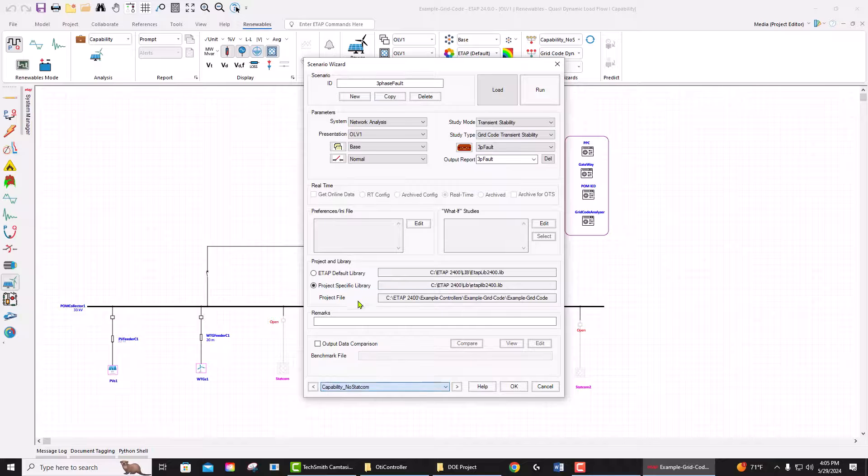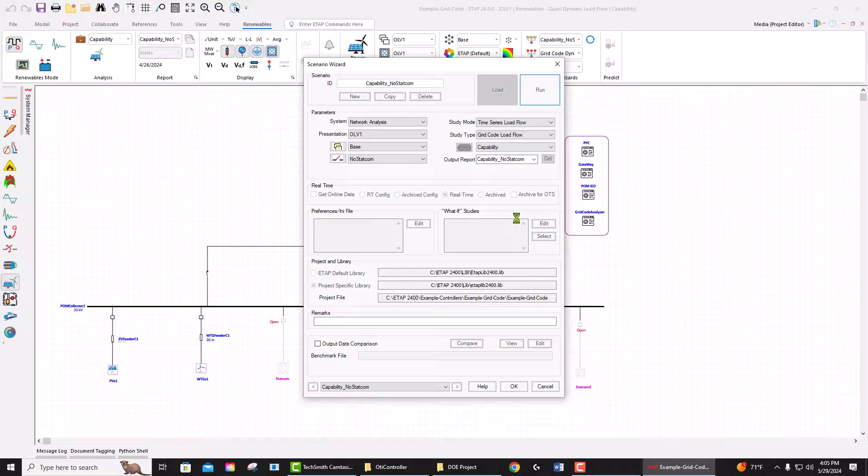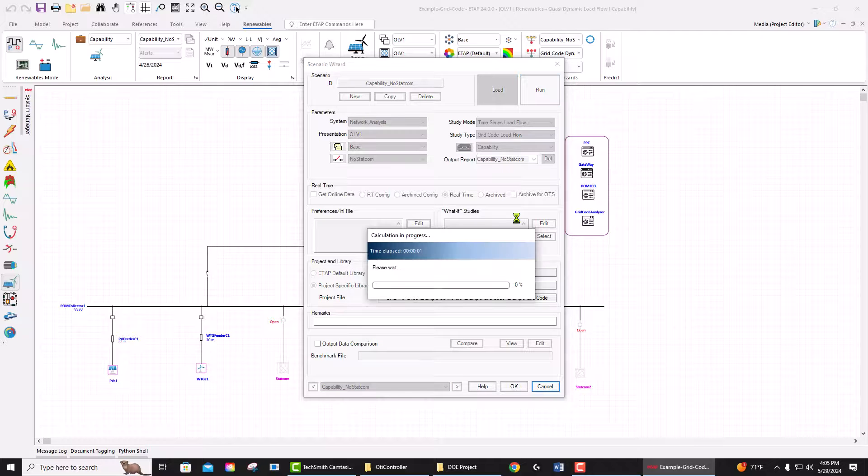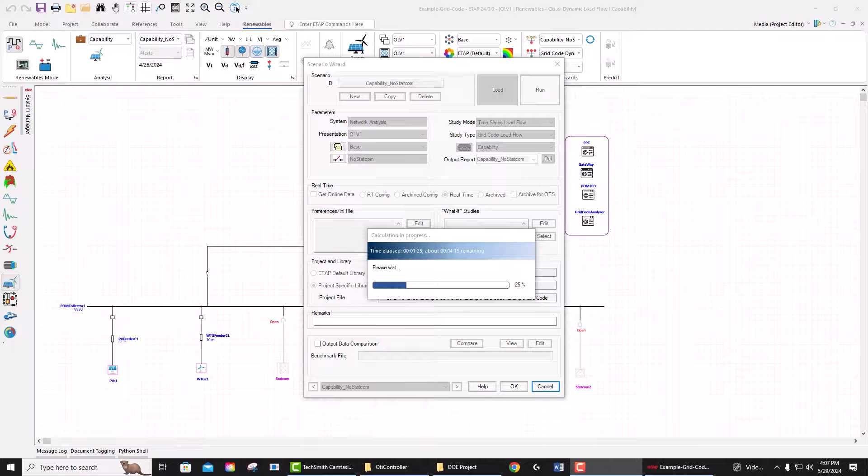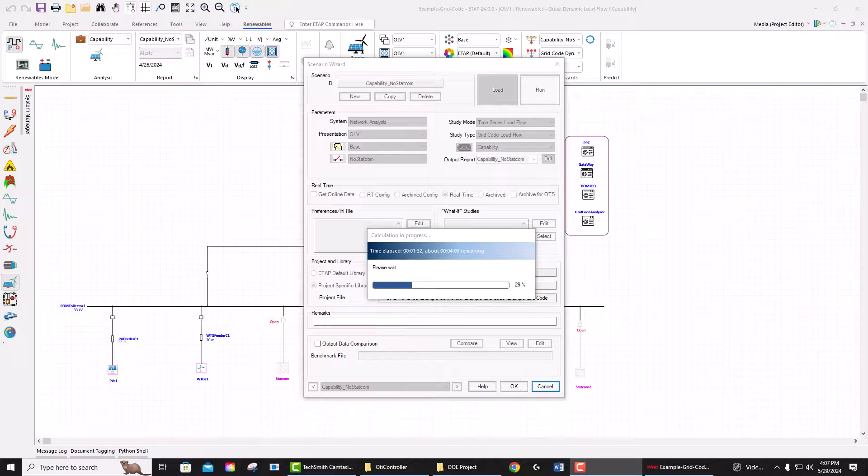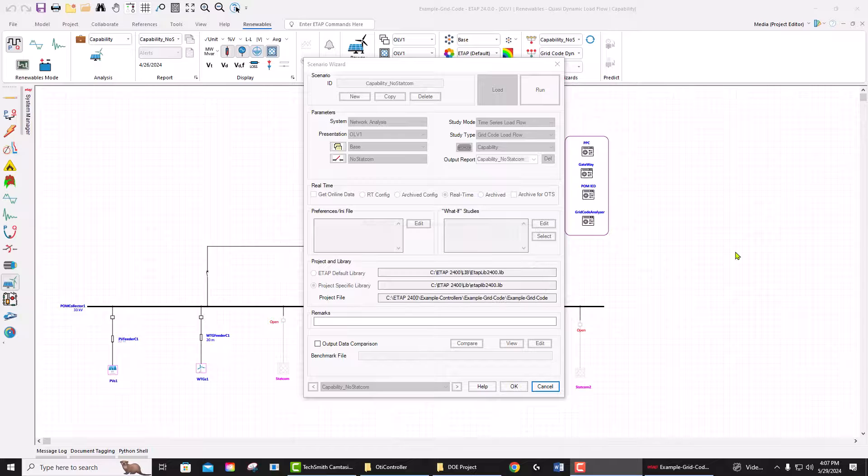Run this, and it basically gonna sweep the PQ and QV curves and determine the capability of this plant and create the Excel report. This may take some time as ETAP gonna run lots of load flows to find the PQ and VQ capability for all different active and reactive power and voltage levels.